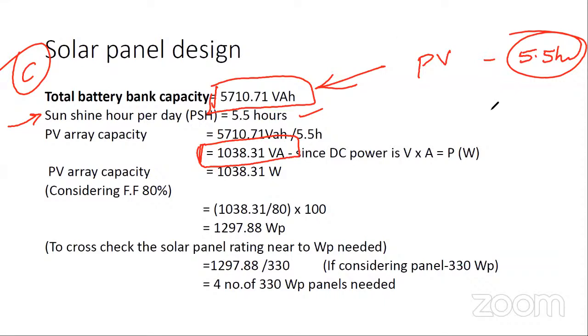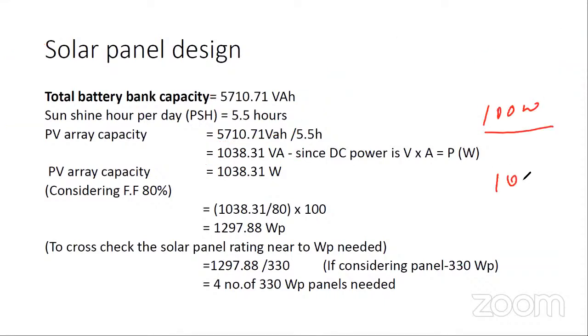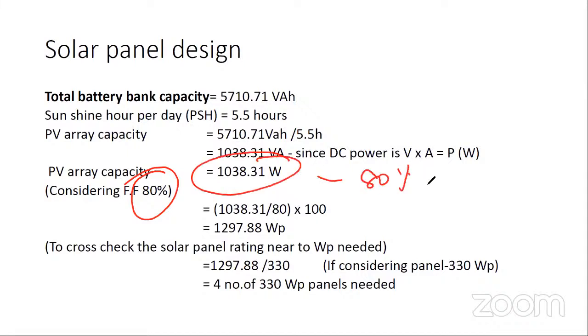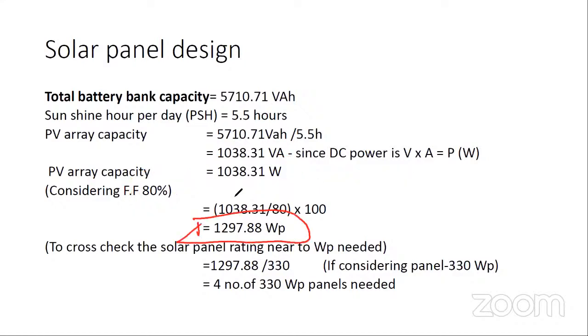But do you think a 100 watt panel will always give 100 watts as a practical output? Temperature, dust, cable losses, all these things. So that's why I'm considering only a fill factor of 80%, which means I'm going to get only 80% of the output. Then I need to identify my 100%, so I'm dividing by 80 into 100. So I'm arriving at 1297.5 watt peak as my total PV array capacity.